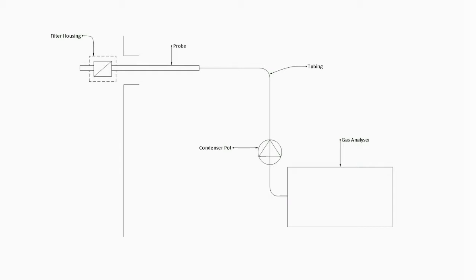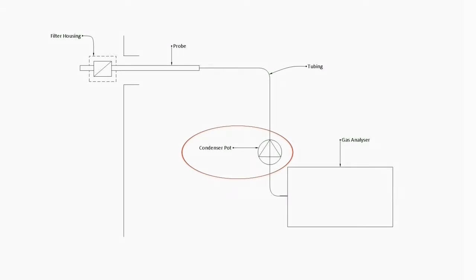The sampling line is also heated to prevent condensation before the sample gas reaches the conditioning system. This is because condensate in the line can absorb some gases before they reach the analyzer, skewing the accuracy of the measurements.